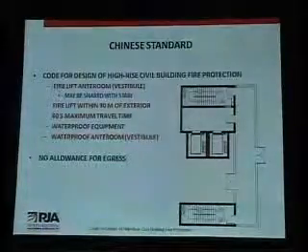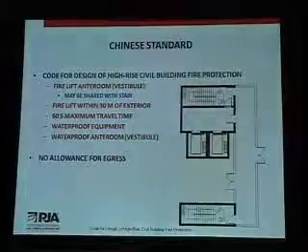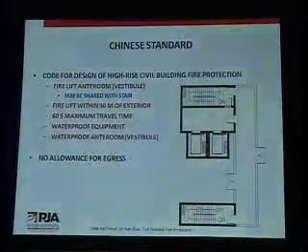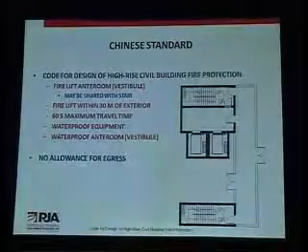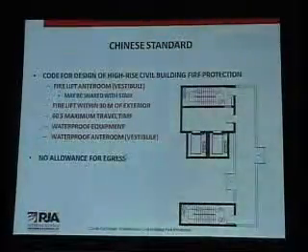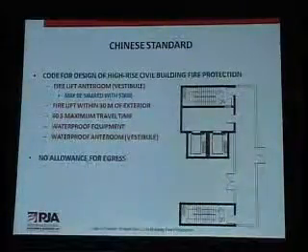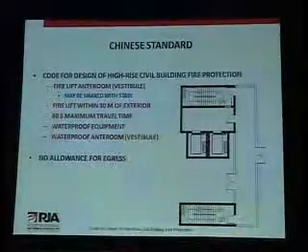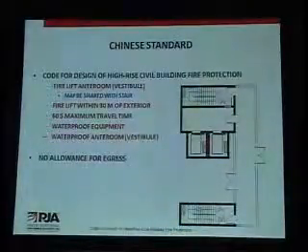Another very interesting requirement that isn't present in the U.S. codes or the European Union standards is that the fire lifts need to be within 30 meters of an exterior building so that the fire service can get in and easily access the lifts without having to transport their equipment long horizontal distances before they get into the lifts.